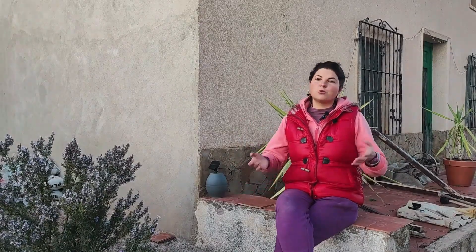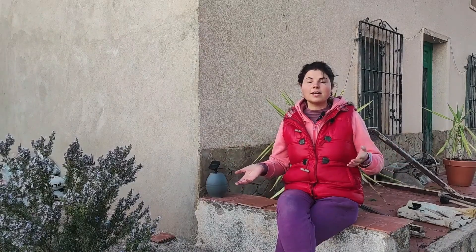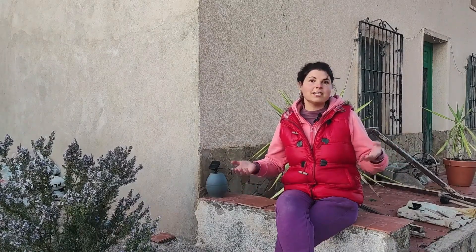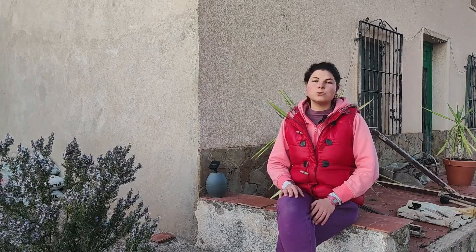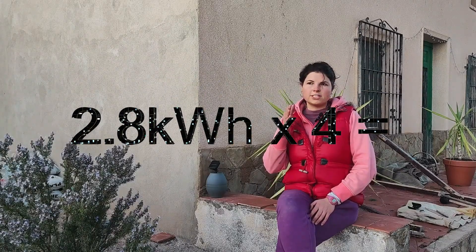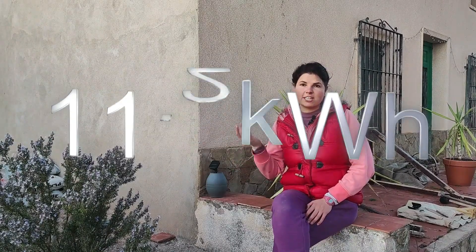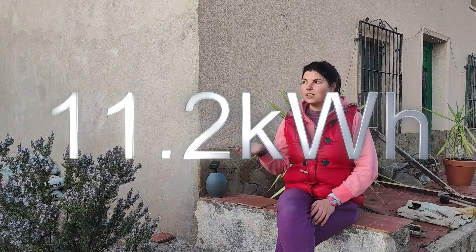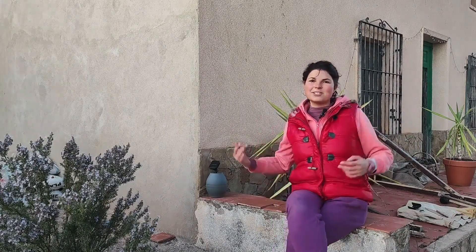The production is limited to daytime and will vary from winter to summer. For winter in my area I have nine hours of sunlight per day on average. To be pessimistic I'll take four hours as my conservative estimate of productive hours. So I multiply 2.8 by four hours per day to get my average daily production: 11.2 kilowatt-hours.